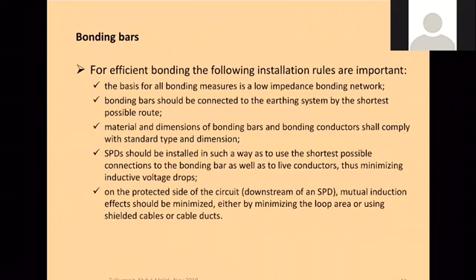For efficient operation of the bonding bar, the following rules are important. It has to be of low impedance, and should be connected to the earthing system by the shortest possible route rather than a longer one. Material and dimension of the bonding conductor shall comply with the standard. There are certain dimensions that you need to comply with, and the SPD should be installed so that there is the shortest possible connection to the bonding bar. For example, your red phase needs to go to the bonding bar, so the SPD should go straight to the bonding bar, as short as possible. Or yellow phase, blue phase, neutral, through SPD. But the ground wire from the power line goes straight to the bonding bar. Okay.